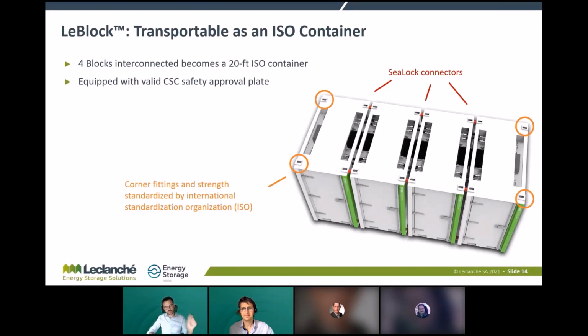On top, we have an interconnection section that's identical on each block. In each connection section we have the DC high voltage connections, the auxiliary connections, and the liquid cooling connections.